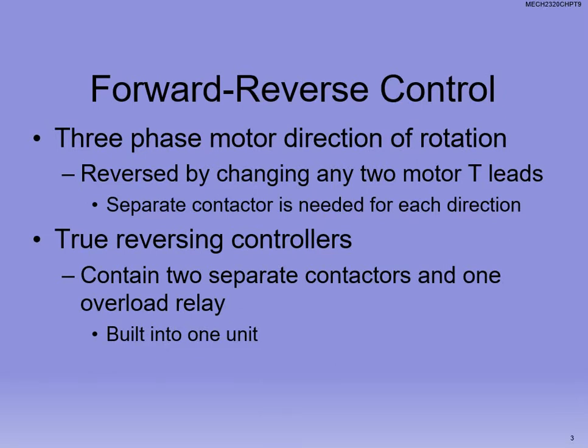If we want to talk about reversing a three-phase motor, we can reverse it by changing any two of the motor leads — one for the other. I'll show you on a schematic on the next page. Separate contactors are needed for each direction. Ideally, true reversing controllers use two separate contactors and one overload relay.